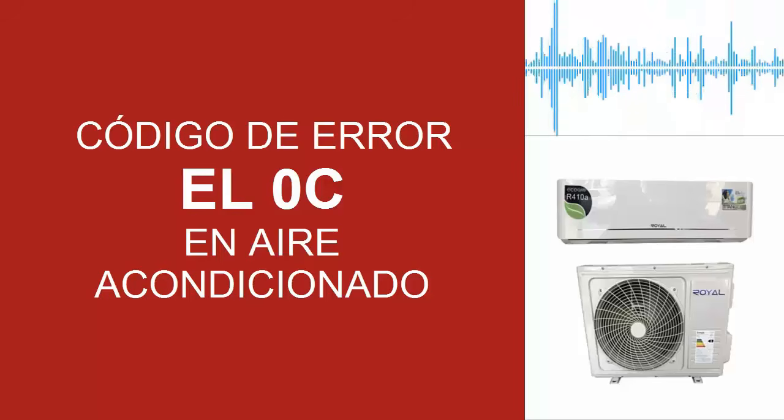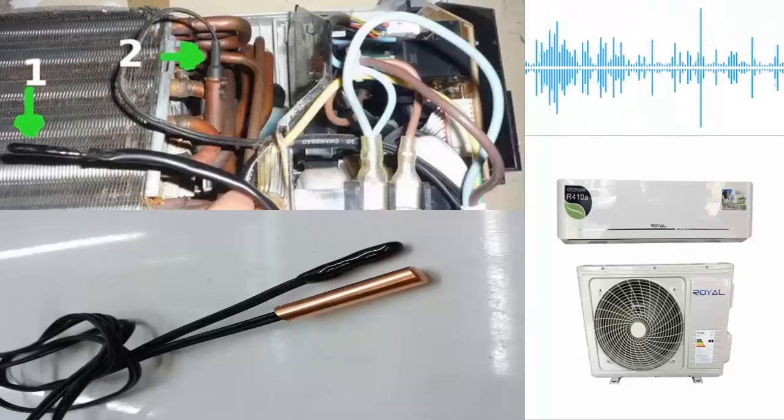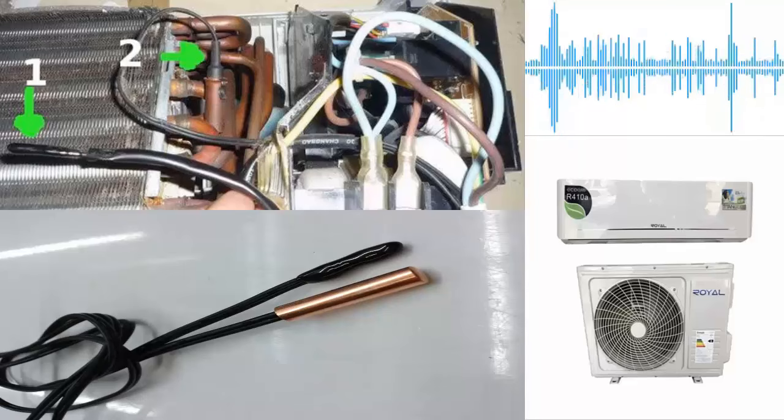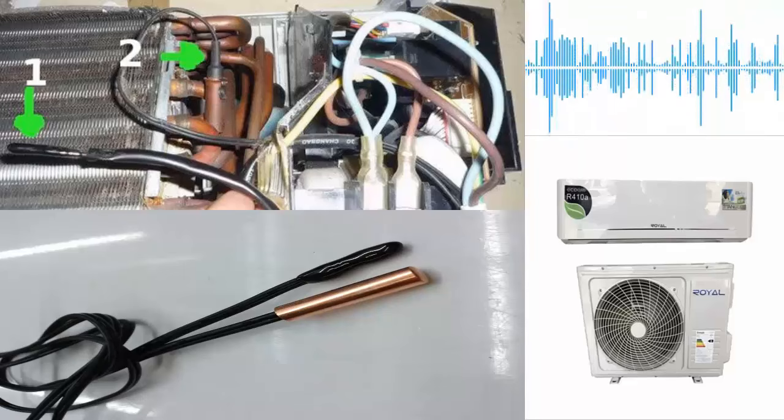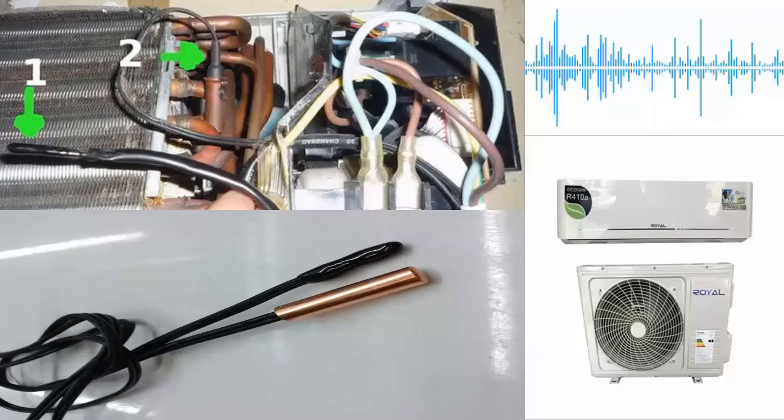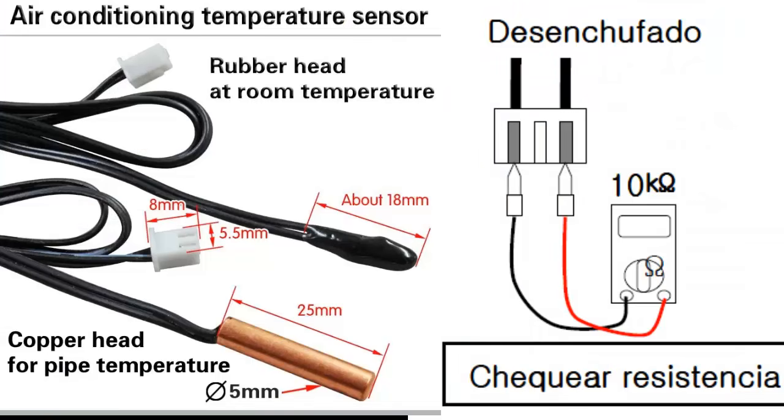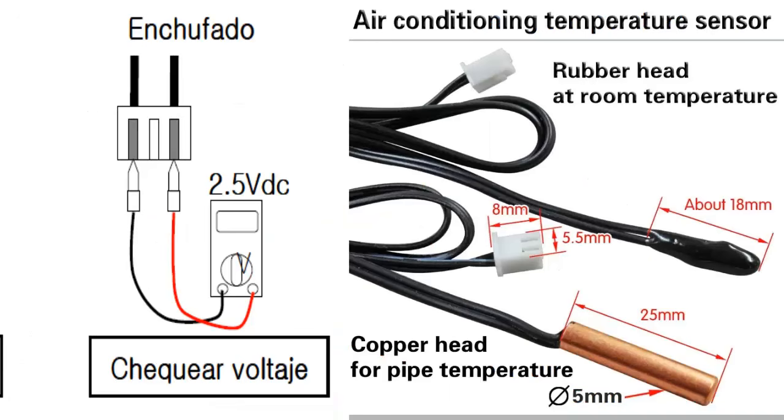C. If a temperature sensor is poorly placed or calibrated, an alarm may occur. Verify the temperature sensor's electrical resistance with a digital multimeter. Disconnect it to test with the multimeter set to kilohms. It should never read infinity or zero. When rubbing it with your hand, the multimeter's resistance reading should decrease. Also, check if the card feeds the sensor correctly by connecting the sensor.